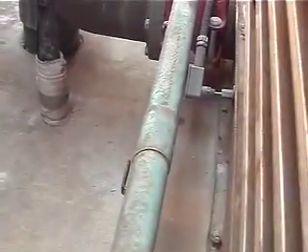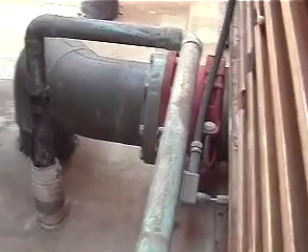Exactly. If we did that, it would require a little bit of thought as far as putting some heat trace on this line here, or at least wrapping it really well. You still have to drain it, but that small amount of water would freeze a little easier. If you look at that sensor, that's your sub-temperature sensor. It's just a well inside there that we're using for monitoring. If we don't control off that sensor, it's just going to say, hey, you're too cold, and issue an alarm.